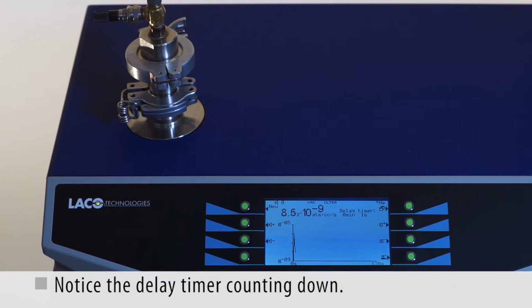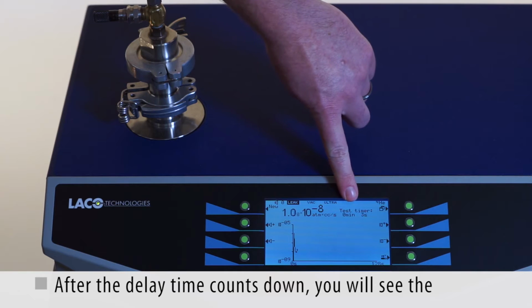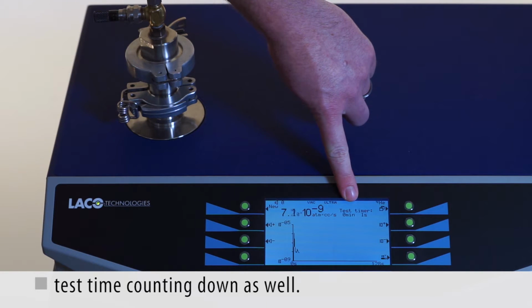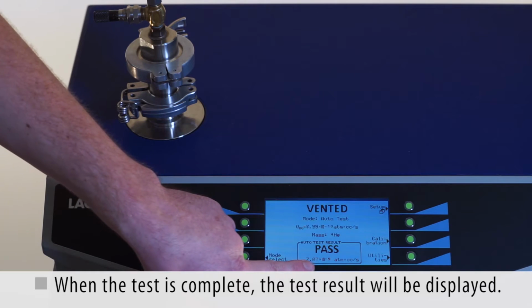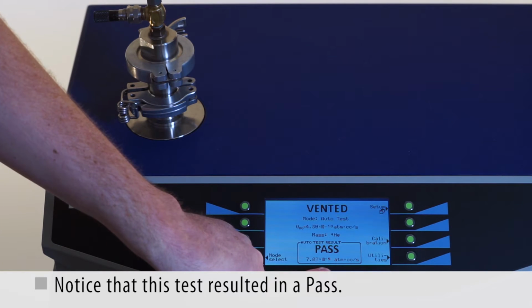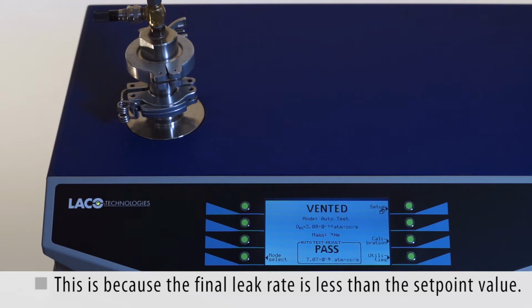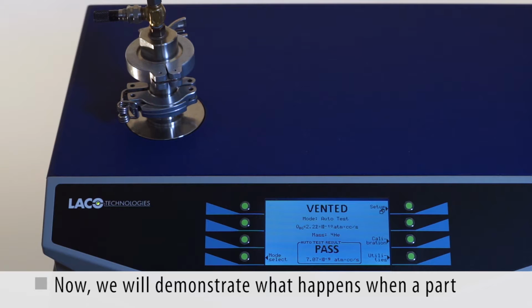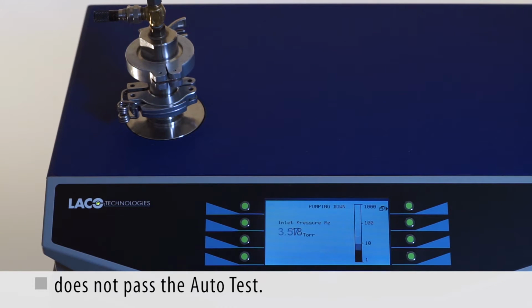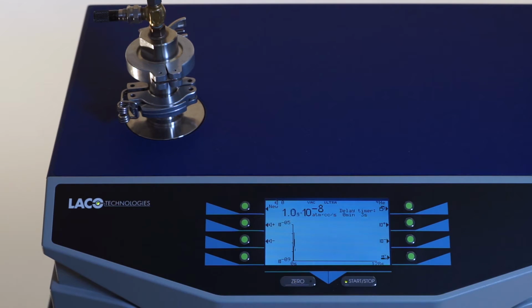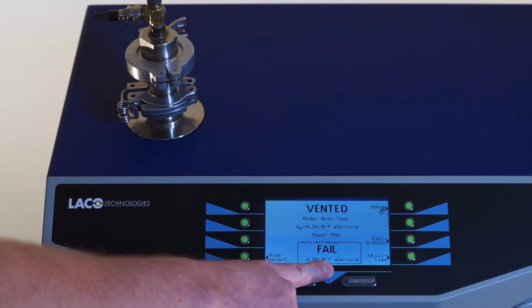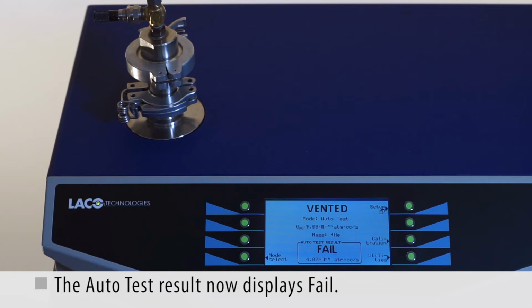Notice the delay timer counting down. After the delay timer counts down, you will see the test timer counting down as well. When the test is complete, the test result will be displayed. Notice that this test resulted in a pass. This is because the final leak rate is less than the set point value. Now we will demonstrate what happens when a part does not pass the auto test. The auto test result now displays fail.